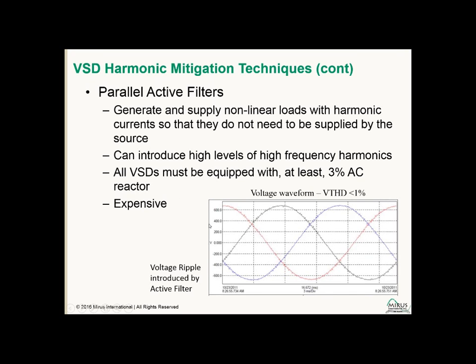Before we leave the parallel active filters, I just wanted to show you a voltage waveform that was measured at a site that I was at where an active filter had been installed. You can see the high frequency ripple on the voltage. The overall voltage distortion at this site was very low. It was actually less than 1%. But all of that voltage distortion was at this high frequency.